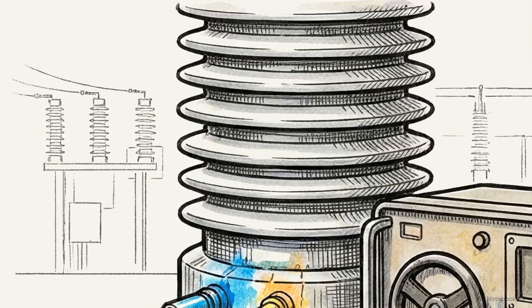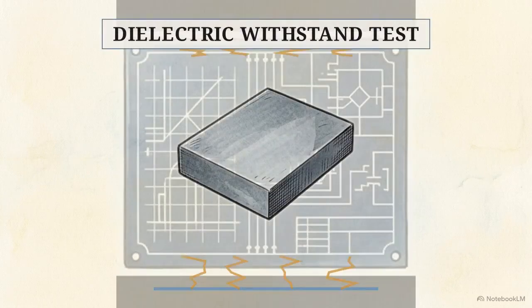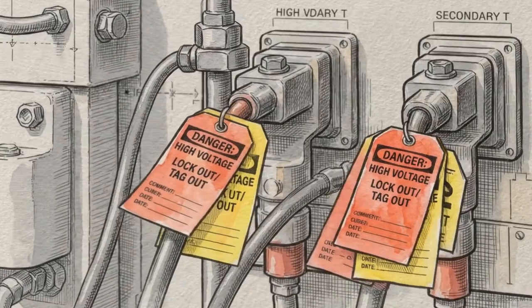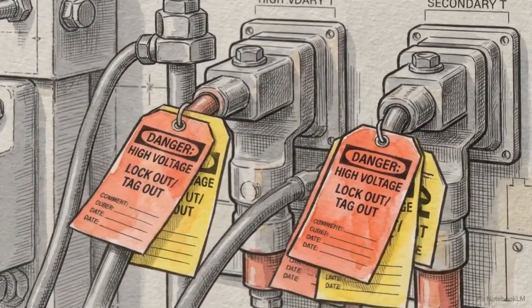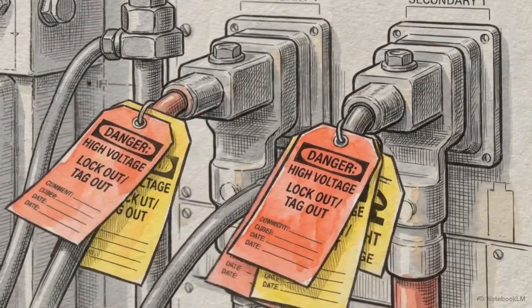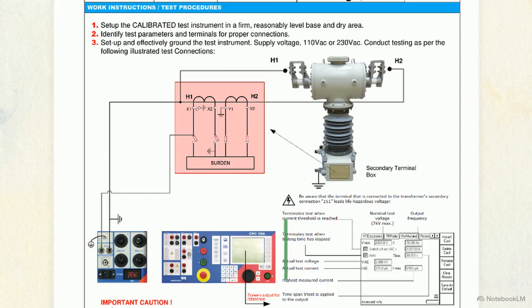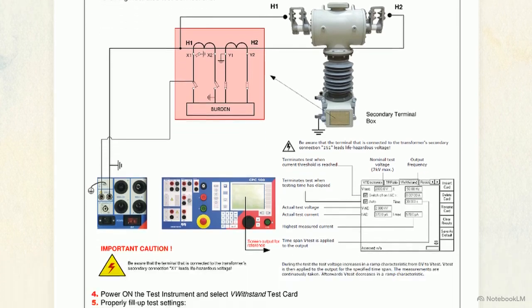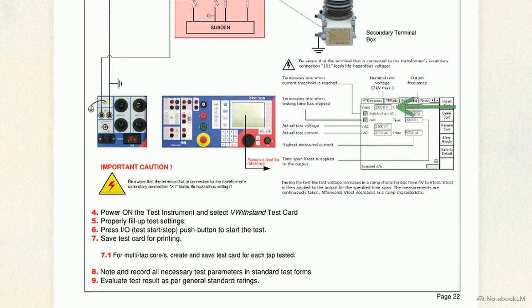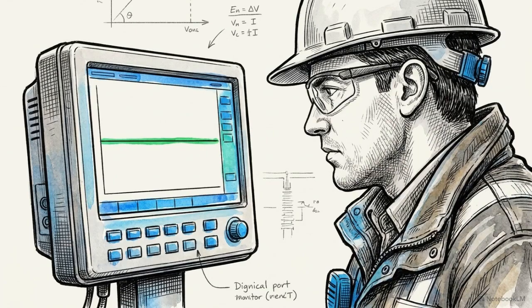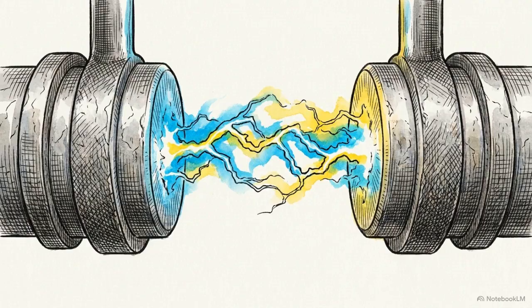Next is the high-voltage dielectric withstand test. Here, the secondary insulation is subjected to the maximum electrical stress it is rated to survive. During this procedure, the secondary terminals will actively carry lethal AC test voltages reaching up to 2 kilovolts. Before initiating the sequence, technicians must establish a strict physical exclusion zone around the testing boundary and implement direct communication controls. The CPC-100 is programmed to carefully ramp the voltage up to the target threshold, hold it for the specified time span, and then ramp it down continuously to 0. Throughout the hold phase, the operator monitors the unit for any signs of insulation breakdown, arc flashover, or asymmetrical leakage currents that indicate a compromised dielectric boundary.